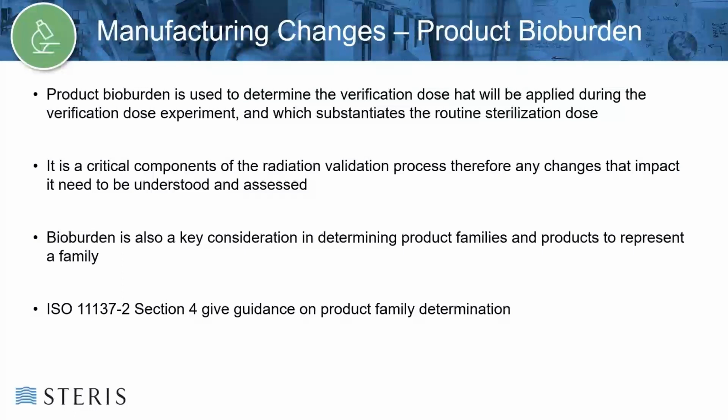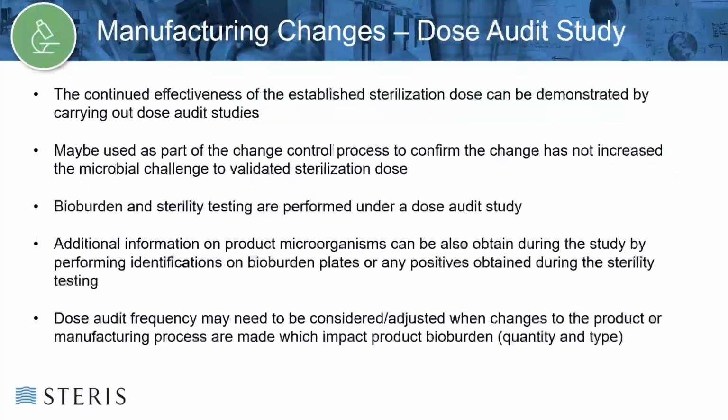ISO 11137-2, Section 4.4.2 also states modifications to product and/or modifications to the manufacturing process shall be assessed through a formal documented change control system. The continued effectiveness of the established sterilization dose can be demonstrated by carrying out dose audit studies.